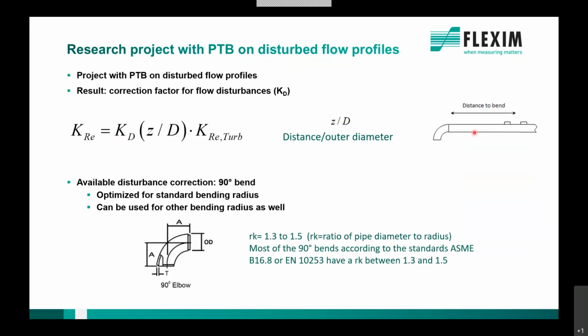And even though it's shown in that picture that we install the transducers in the same plane as the 90-degree elbow, for us it doesn't matter in which plane we install it. That's taken into account, so you can install it in any plane, because sometimes you don't have access to all of those planes, and especially not to the best one. That's why we do not say which is the best one. Install it as you can, and according to all other restrictions or recommendations for the installation.